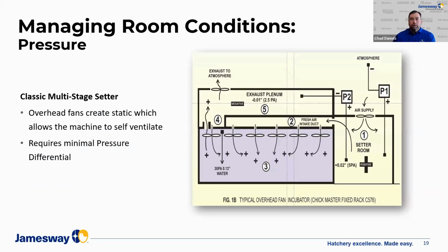So if we take a quick look at some of the incubation equipment that is in use today, the classic multi-stage setter that was originally built by Chickmaster kind of comes to mind. What this machine provides an example of is a machine that has fixed speed fans internally. And when these fans come on, they create a severe negative in the fresh air intake duct above. And by doing so, it creates a natural draw of air from the room into the machine. And then from there, the machine exhausts into the plenum where it goes to the atmosphere.